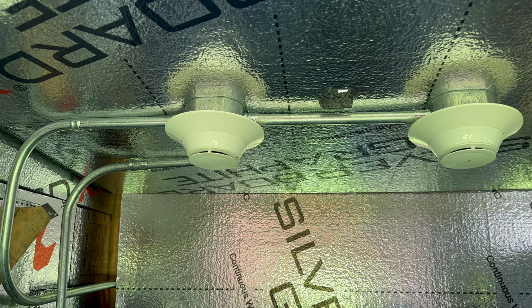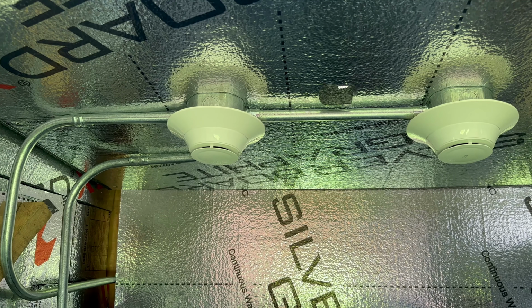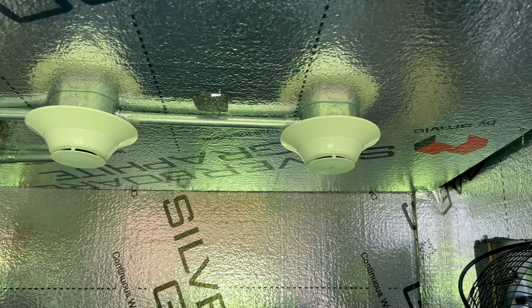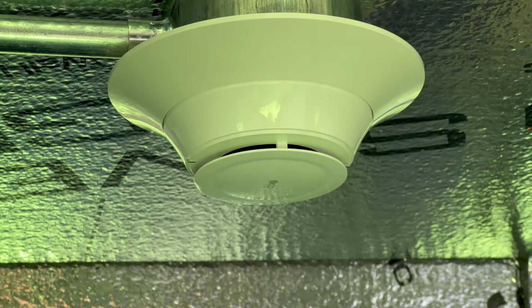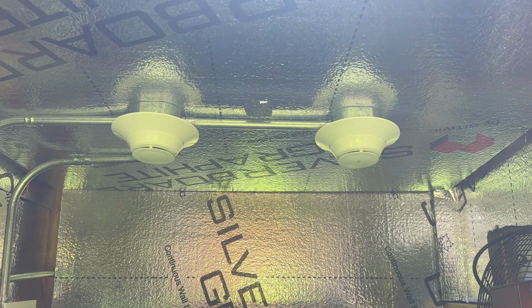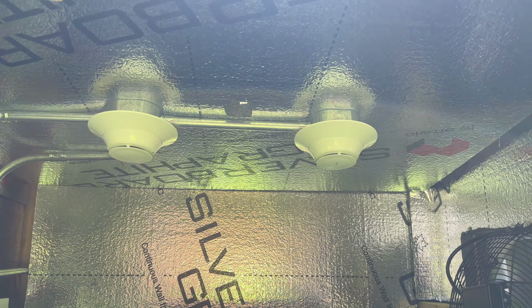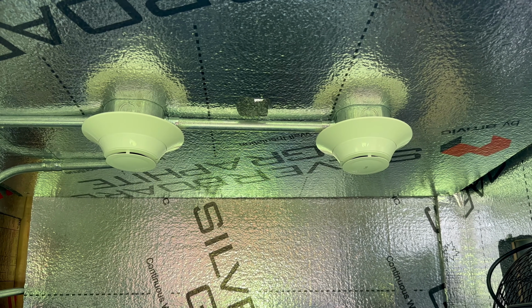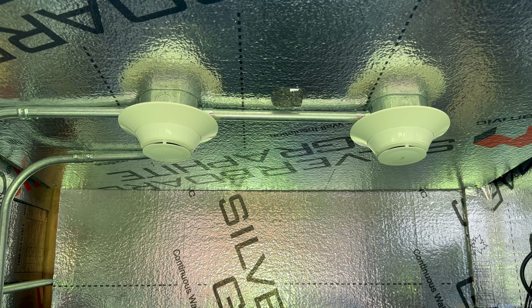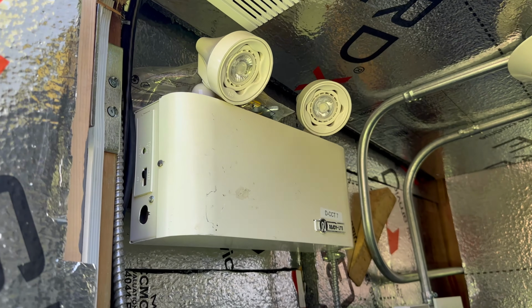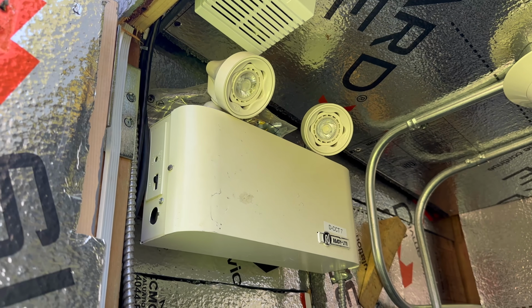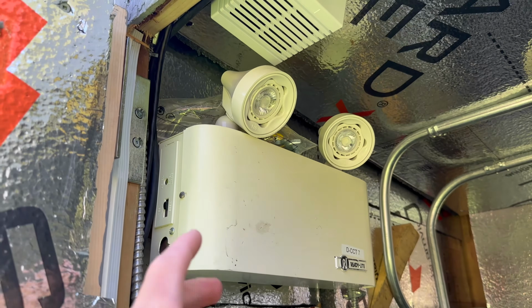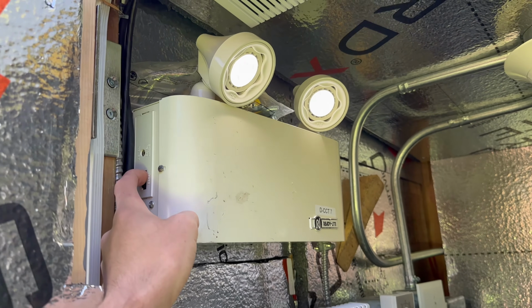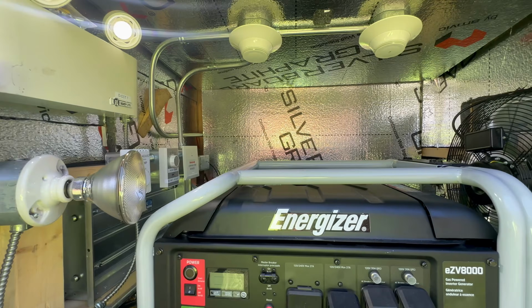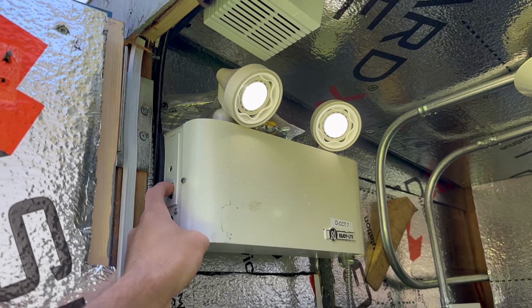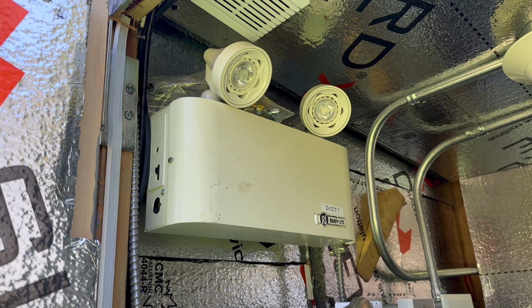So we have smoke detection for any small smoldering fires that may start, and for anything that quickly gets out of hand, we have a heat detector which activates at 57 degrees Celsius. Both of those are tied into the fire alarm system and will put the system into full alarm, setting off all of the horns and strobes, and will give me an alert on my phone that the fire alarm system has activated. We also have emergency lighting in here should the generator fail to start automatically and someone needs to come out. This emergency light will come on automatically upon power failure and help illuminate the building, which is important because oftentimes the power outages are at night and that could be when you need to get out here.